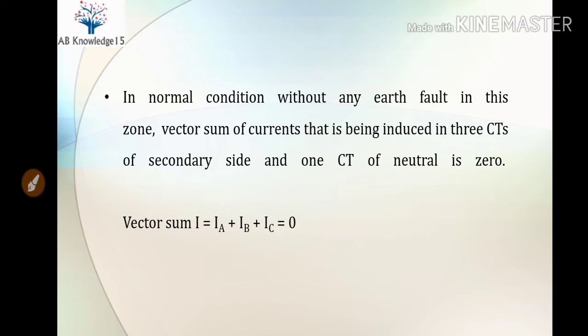In the normal condition of the transformer, without any earth fault in this zone, the vector sum of currents induced in the three CTs of the secondary side and one CT of the neutral side is zero. So the vector sum I equals Ia plus Ib plus Ic, and all three phase vector sum currents will be zero in the normal condition.